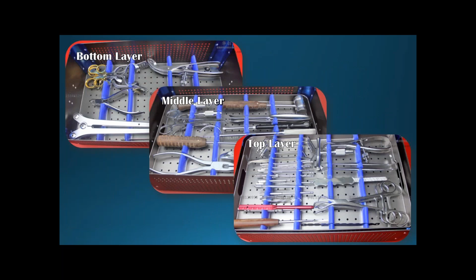And with these, you have to make sure that you're checking temperature and weight and things like that, to make sure that they're not too heavy. A lot of places use rigid containers anymore so that they reduce the risk of tears in their wrap sets, so that there are no holes in their sets, and they don't have to recall or reprocess instrument sets due to holes in the packaging. So this just shows you different layers of a set. When you have a set like this with multiple layers, again, you're putting that class 5 in the most challenging place in those different layers.